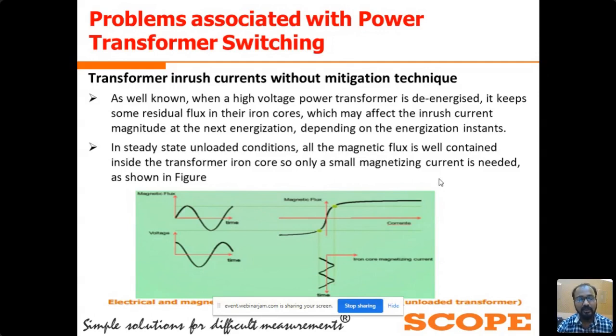That means whenever we randomly de-energize the power transformer without any reference of system voltage, we don't know how much residual magnetic flux is available in the iron cores of the power transformer. In this waveform you can see the relation between the magnetic flux and the system voltage.